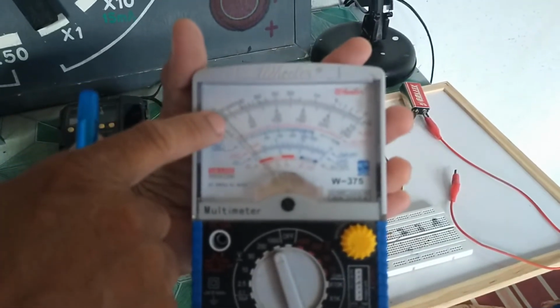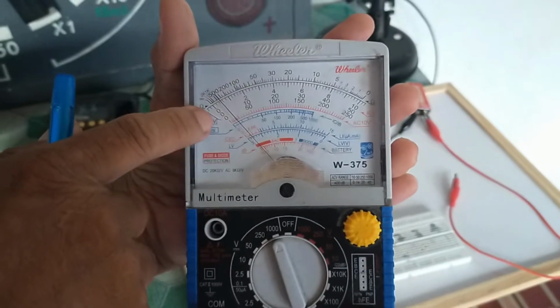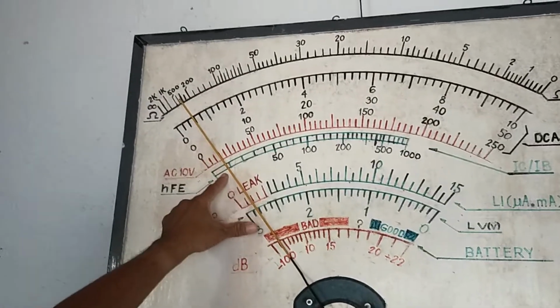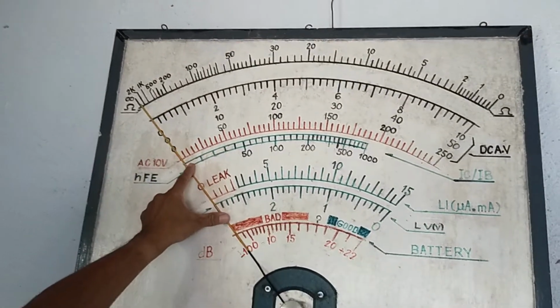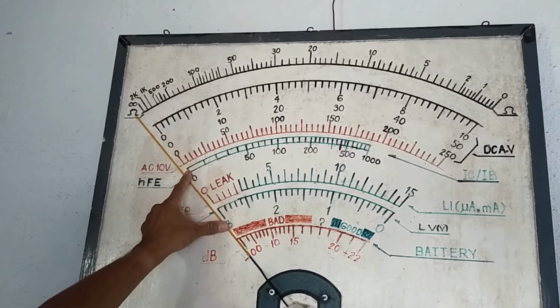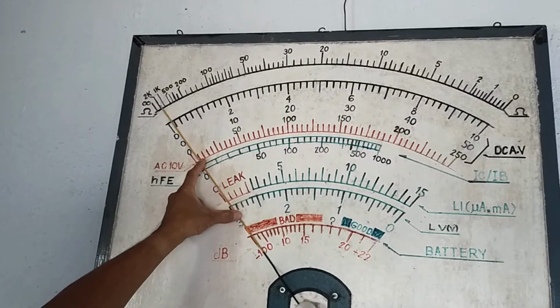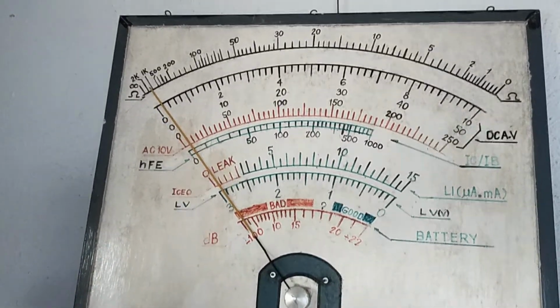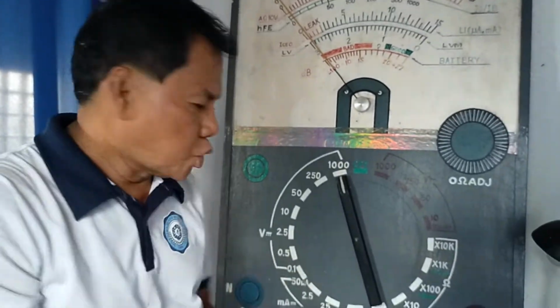You notice, class, that the deflection pointer doesn't position to the 0 scale. It is a little bit advanced, just like this. It should be here. No, not this one here. It should be here, because it will cause error in the reading of current and voltages. So what shall you do?